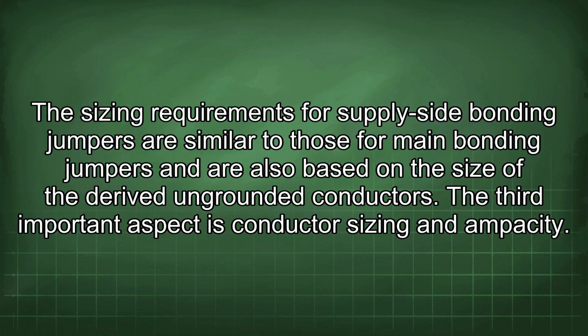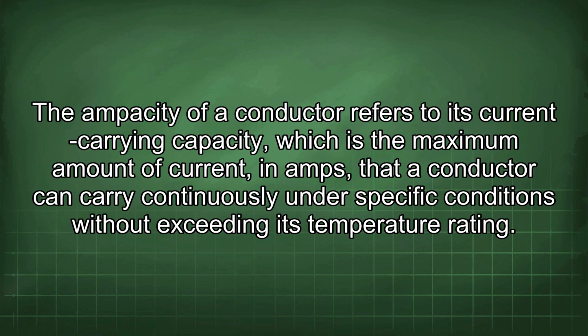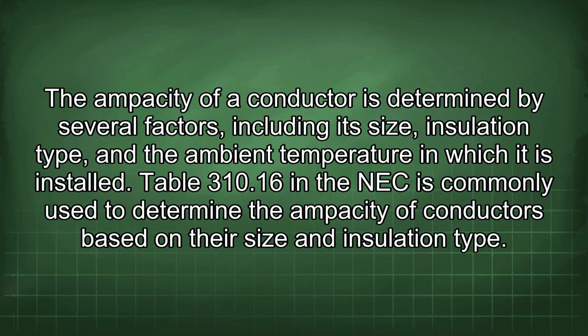The third important aspect is conductor sizing and ampacity. The ampacity of a conductor refers to its current carrying capacity, which is the maximum amount of current in amps that a conductor can carry continuously under specific conditions without exceeding its temperature rating. The ampacity of a conductor is determined by several factors, including its size, insulation type, and the ambient temperature in which it is installed. Table 310.16 in the NEC is commonly used to determine the ampacity of conductors based on their size and insulation type.